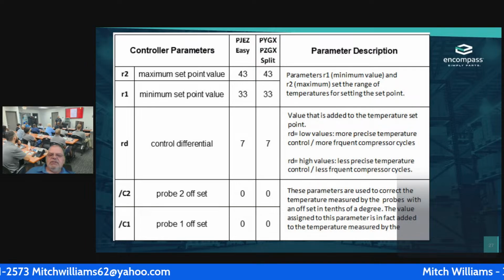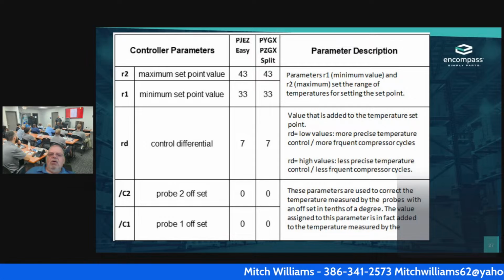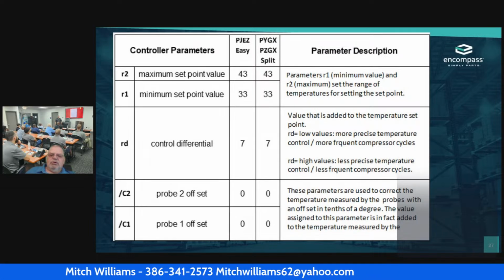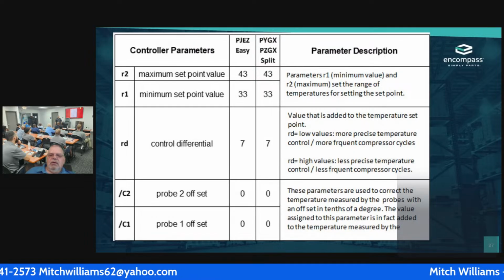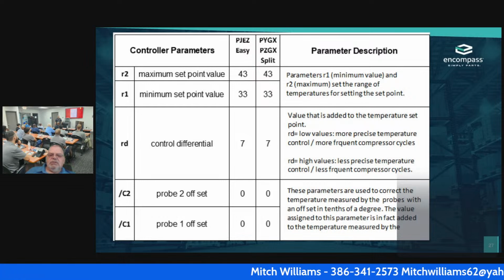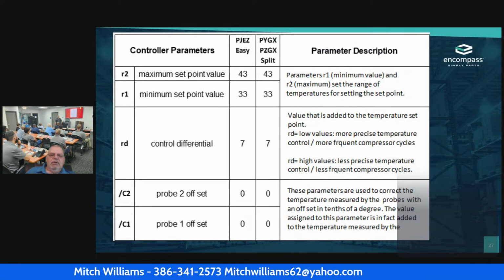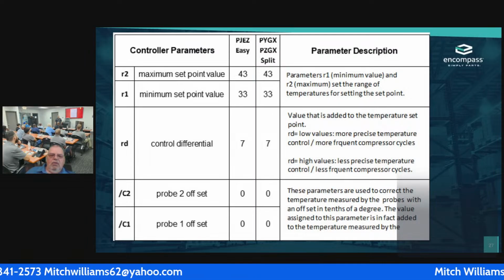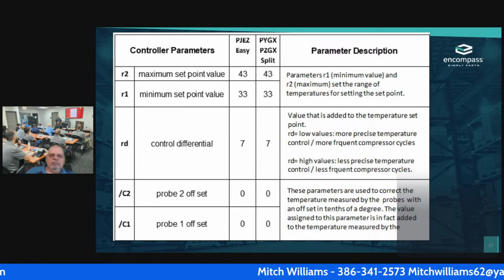Now, if I scroll through again, I get the RD control differential. They're both set at 7. The value is added to the temperature set point. RD low values are more precise temperature control, more frequent cycle controls. RD high values, less precise temperature controls, and less frequent compressor cycles. So I have to be careful whenever I go and adjust the temperature on that, because my RD may throw mine off a little bit.